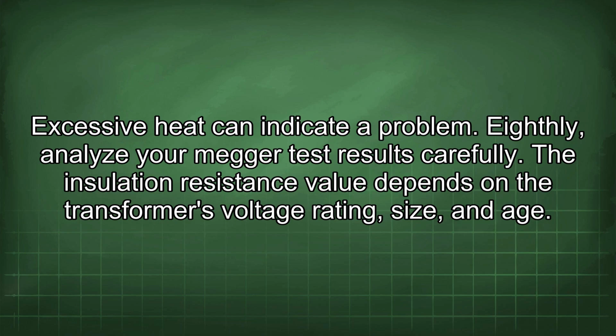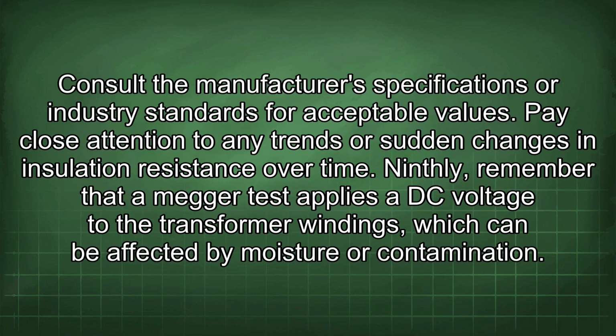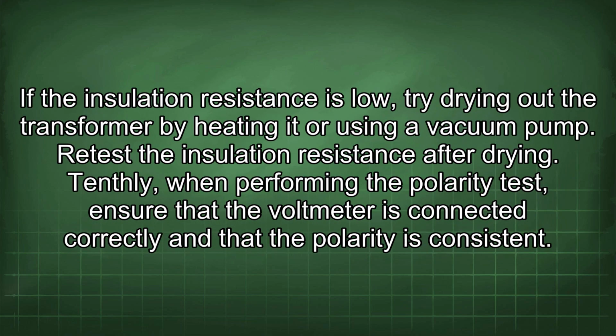Eighthly, analyze your megger test results carefully. The insulation resistance value depends on the transformer's voltage rating, size, and age. Consult the manufacturer's specifications or industry standards for acceptable values. Pay close attention to any trends or sudden changes in insulation resistance over time. Ninthly, remember that a megger test applies a DC voltage to the transformer windings, which can be affected by moisture or contamination. If the insulation resistance is low, try drying out the transformer by heating it or using a vacuum pump. Retest the insulation resistance after drying.